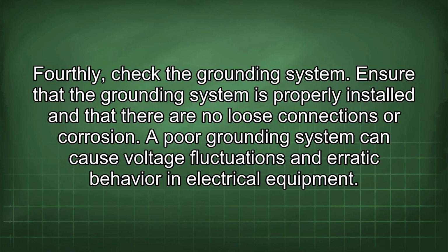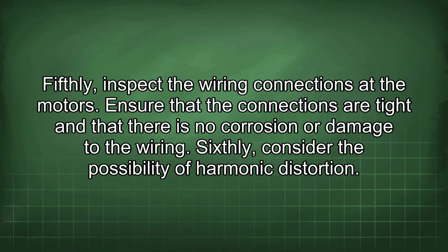Fourthly, check the grounding system. Ensure that the grounding system is properly installed and that there are no loose connections or corrosion. A poor grounding system can cause voltage fluctuations and erratic behavior in electrical equipment. Fifthly, inspect the wiring connections at the motors. Ensure that the connections are tight and that there is no corrosion or damage to the wiring.